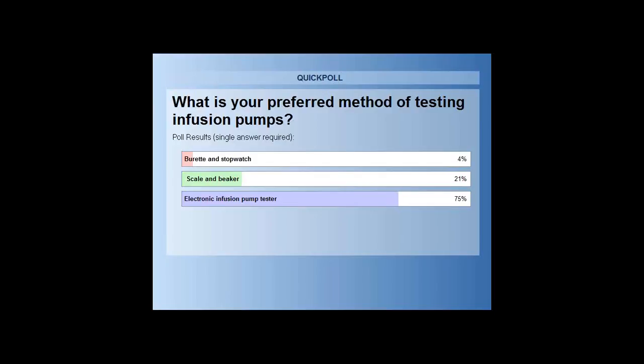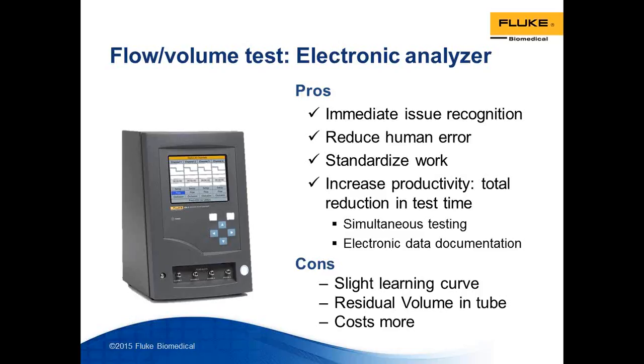with the flow volume test method with an electronic analyzer, now Ed mentioned that there are various types of analyzers. Some are based on infrared technology. Some are based on bubble technology. So this is something you have to be very careful of, because some of these methods are proven, some are not. They're new. So be very careful when you're going with an electronic analyzer in terms of which technology the measurement is actually based on.